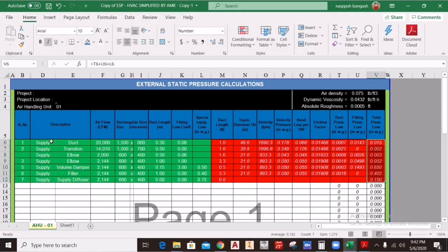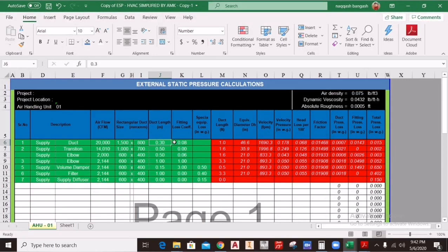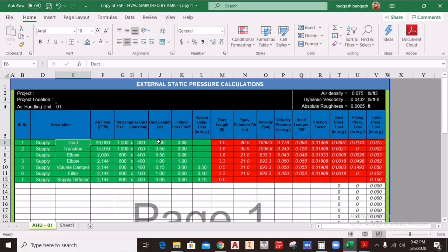We will start from this Excel sheet, which I will share with you to calculate the external static pressure. You need the supply airflow, exhaust airflow, or return airflow, along with the duct size, duct length, and the fitting loss coefficient. For example, you are providing 20,000 CFM through a 1500 by 800 duct. For a duct length of 0.3, the loss coefficient is 0.08, as defined by ASHRAE for 100 feet of duct. Since we are using ducts below 100 feet, we use 0.08.